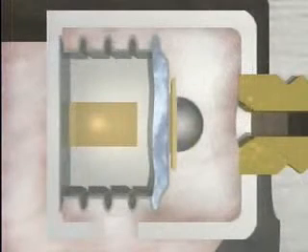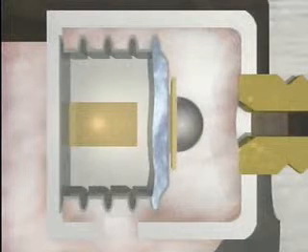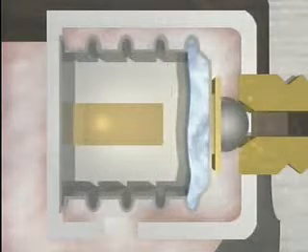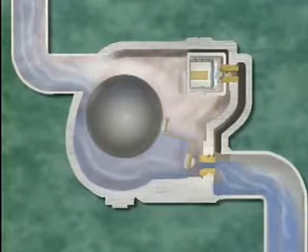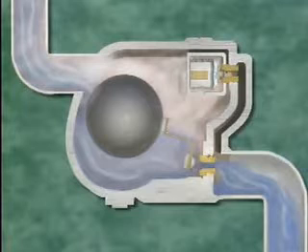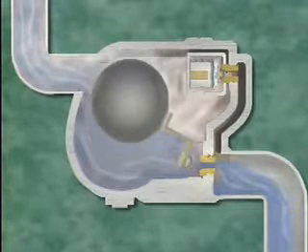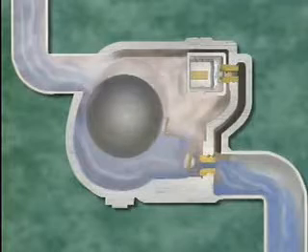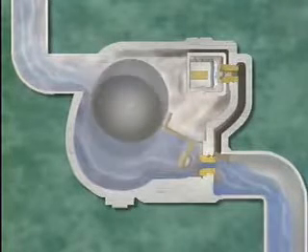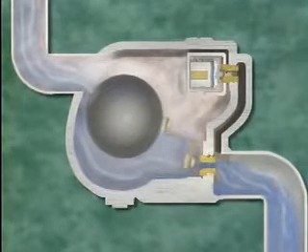When steam enters the trap and reaches the bellows, the bellows expands and the vent valve closes. At the same time, with the main valve open, condensate continues to flow through the trap and be discharged. The changing level of the condensate causes the float to rise and fall, which in turn affects how wide the trap valve opens and how much condensate is discharged.